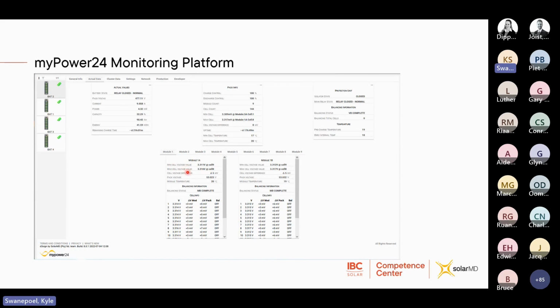So here you can see on this specific module what the lowest and the highest cell is, what that cell delta is, and that individual pack voltage. So we bring it back down to a normal 51.2 volt pack, and then the individual module temperature, and you can go and view each and every single cell in this module, all 16 cells. You'll see what the delta is to the module based on the lowest cell, and then also the pack delta based on where this module falls in line with that pack. All right.